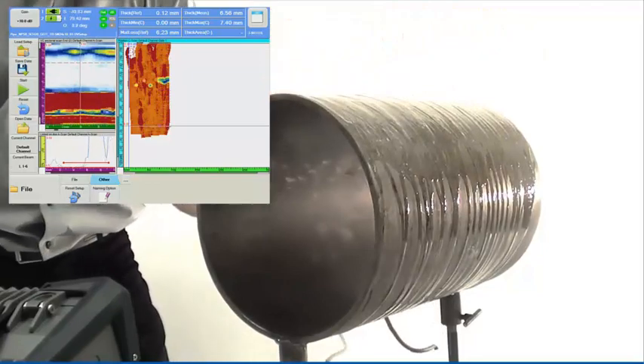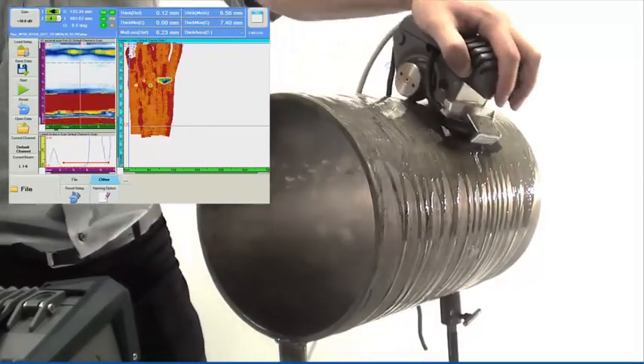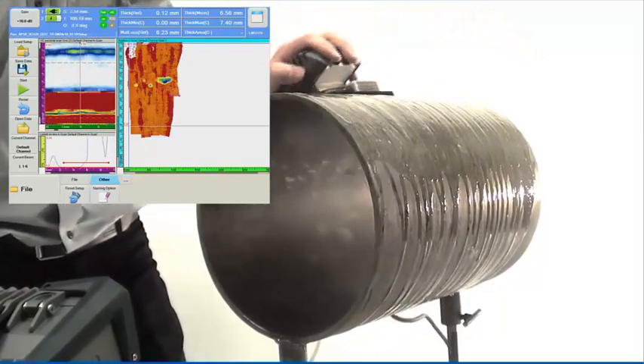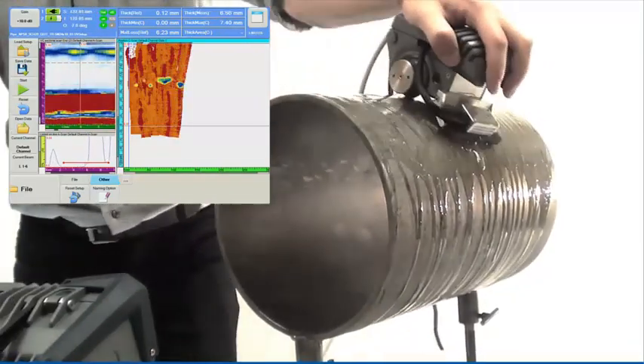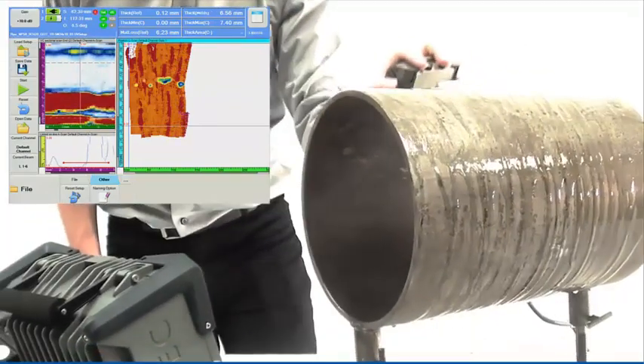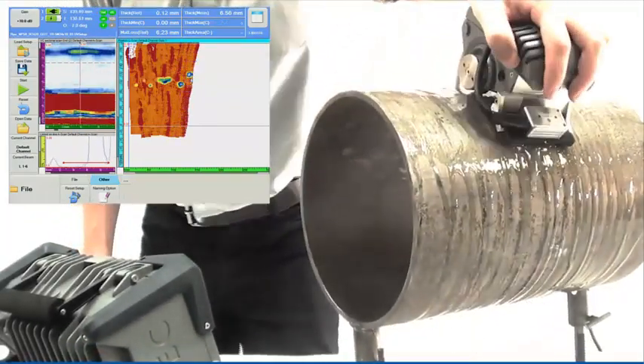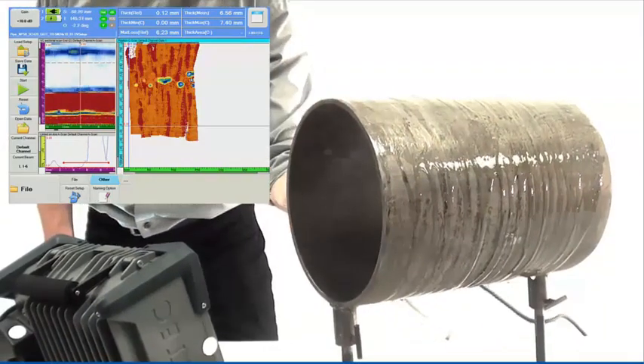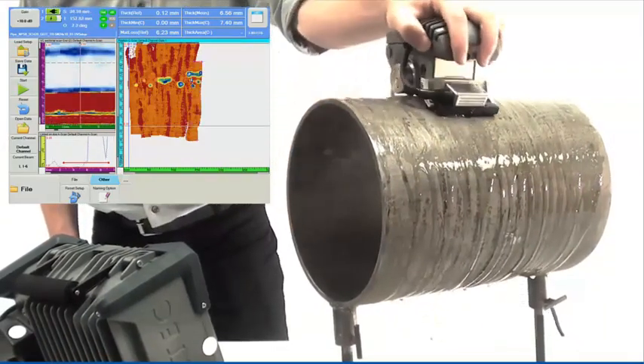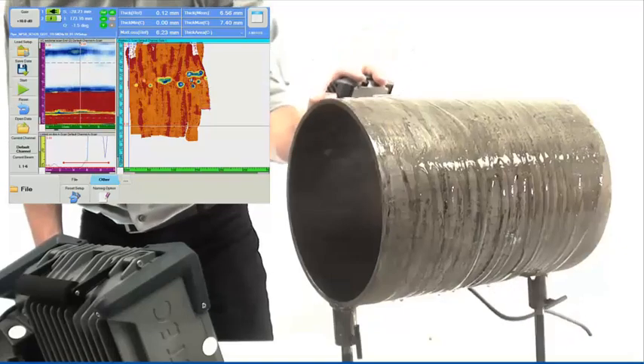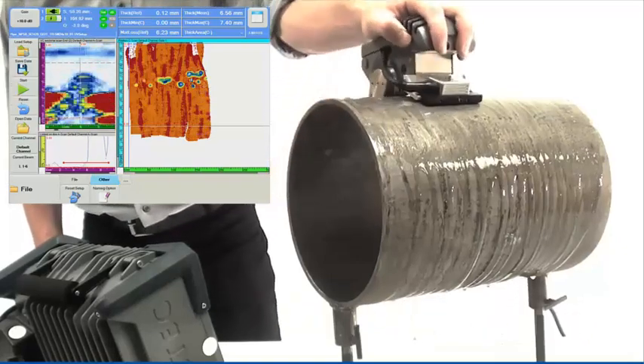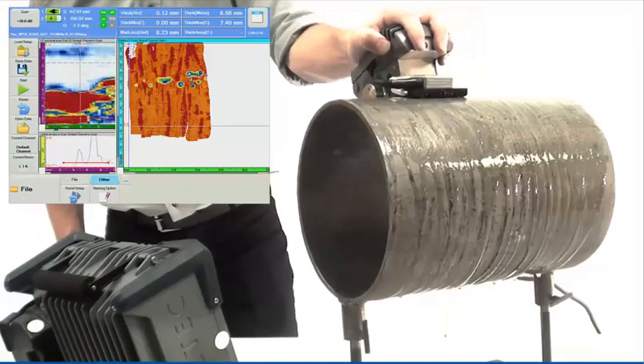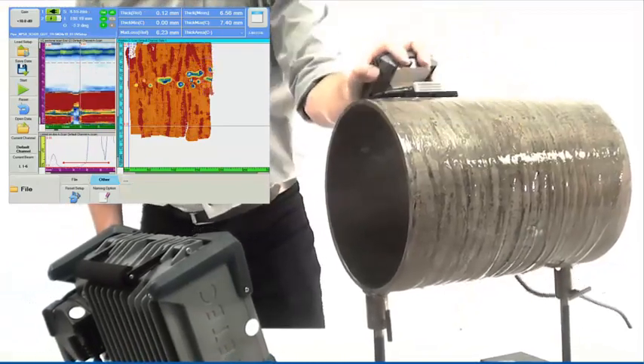The corresponding phased-array UT signals are displayed on the Topaz-16 screen in real-time. Data from successive strokes is accurately positioned on the scanning surface, and the covered area can be easily monitored on the C scan view. This allows the operator to complete the inspection of the entire specimen. Corrosion mapping becomes nearly as simple as painting a surface.